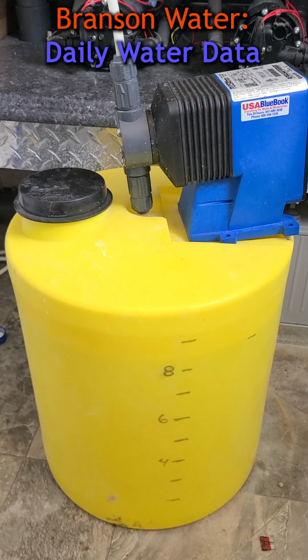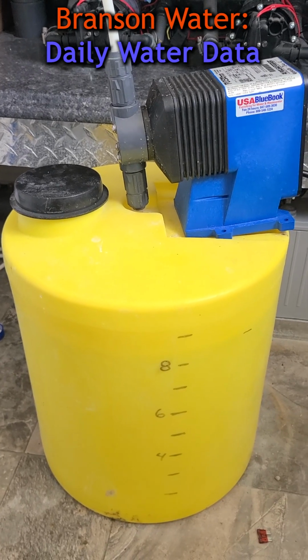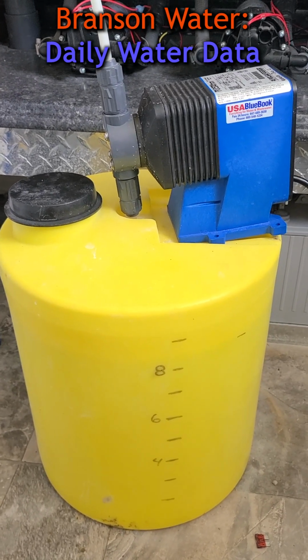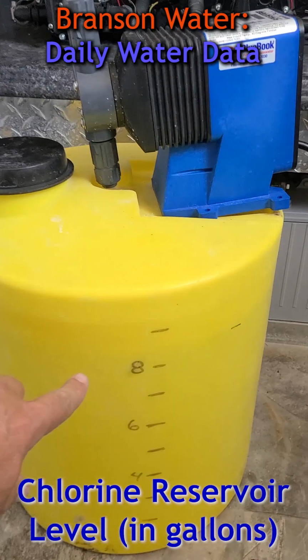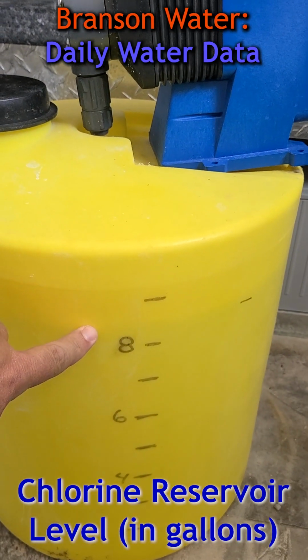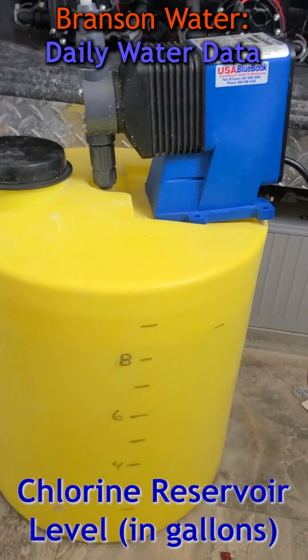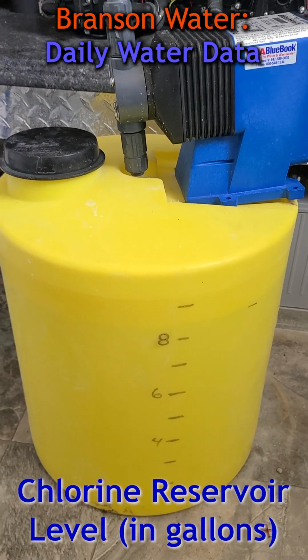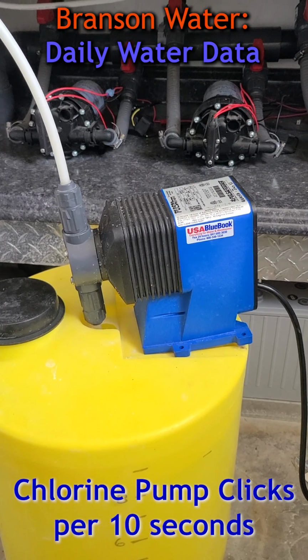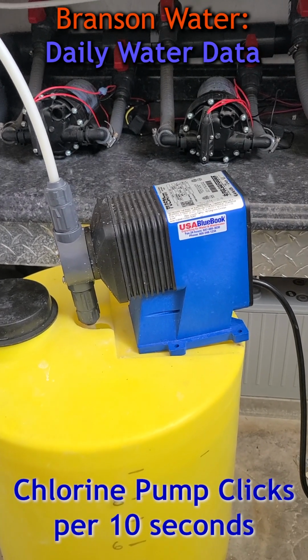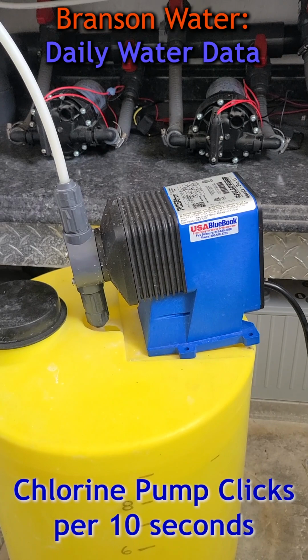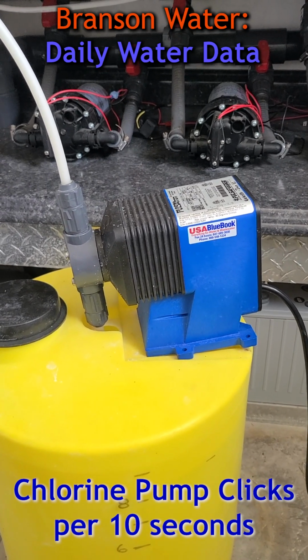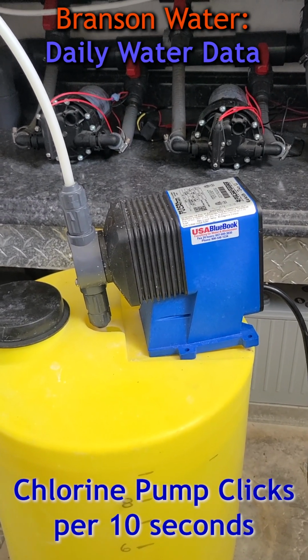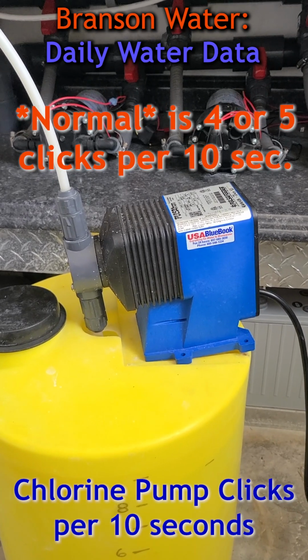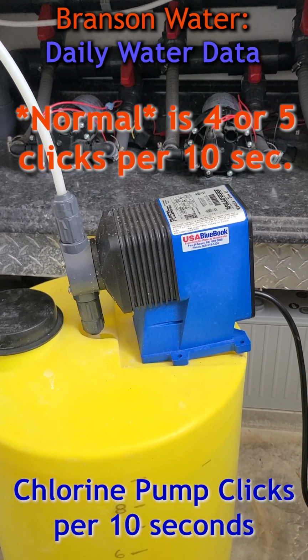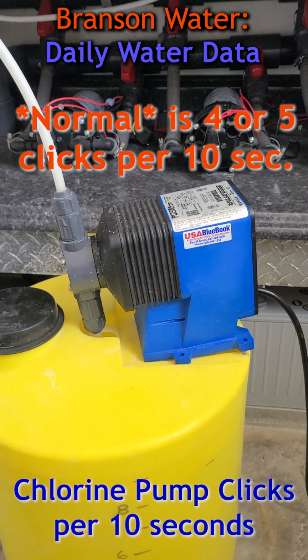The next two pieces of data you're going to record have to do with the chlorine tank and the chlorine pump, which is right here. You can see that the water level inside the tank is right around 8.5 gallons. You're going to indicate that on the data sheet and on the Google form. The next piece of data you're going to gather is how many times the pump clicks in 10 seconds. The way you do this is set the timer on your phone for 10 seconds and then count the number of clicks. We typically have this set to 4 or 5 clicks every 10 seconds.